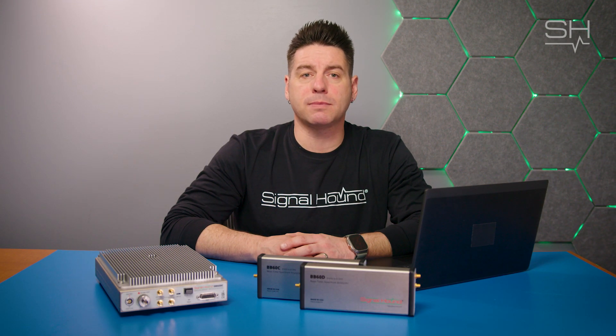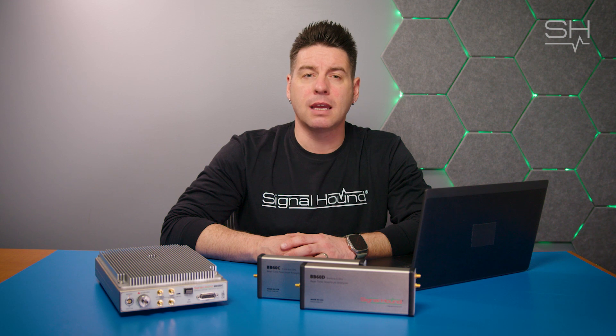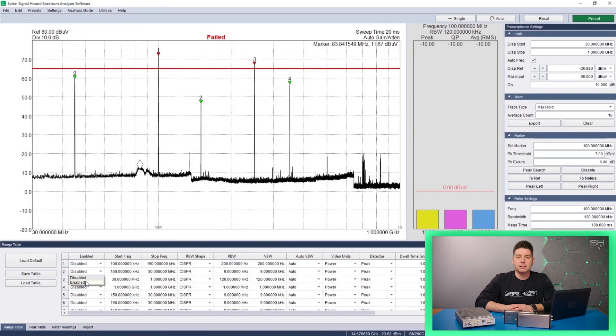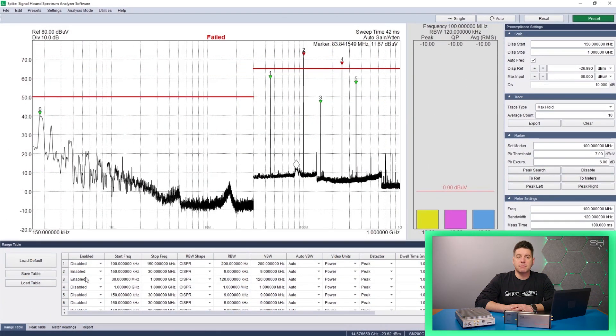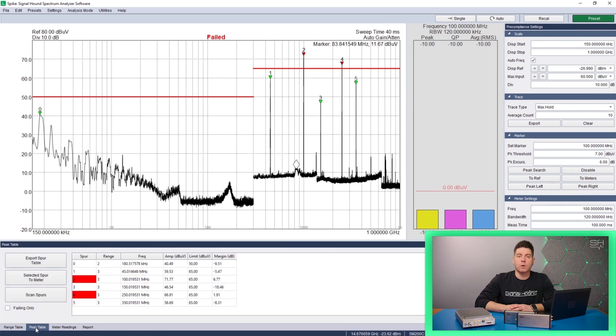Outside of these general-purpose spectrum analysis measurements, you have many targeted spectrum analysis measurements catering to niche industries and tasks. These include measuring harmonics, testing emissions against spectrum masks or EMC pre-compliance limits, and characterizing phase noise or noise figure.